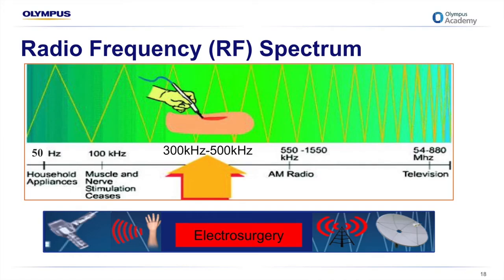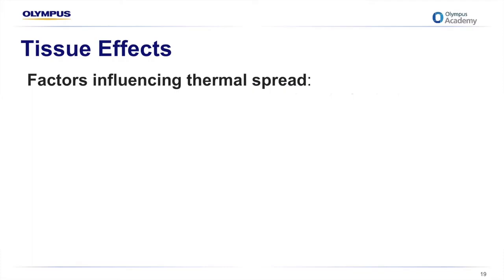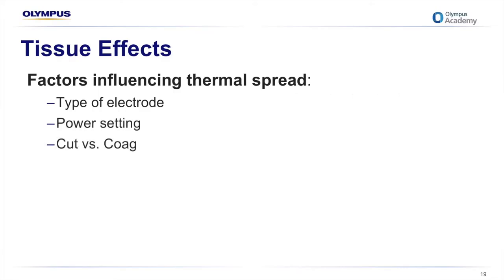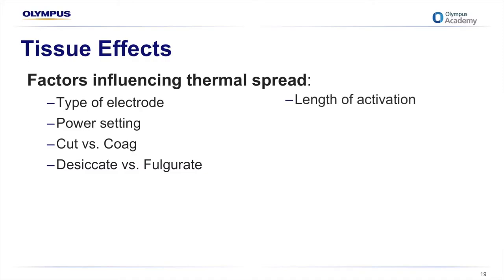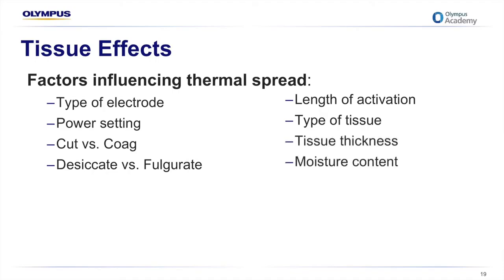So some factors that influence thermal spread, or the tissue effects, and by thermal spread I mean the heat that's built up by the resistance within the tissue. So it could be the type and size of the electrode, the different power settings you use, whether you use a cut versus a coag waveform, a desiccate versus fulgurate technique, the length of activation, the type of tissue you're trying to utilise the electrosurgery on, the thickness of the tissue, and also the moisture content, because you remember, the higher the moisture, the better a conductor of the current it's going to be.